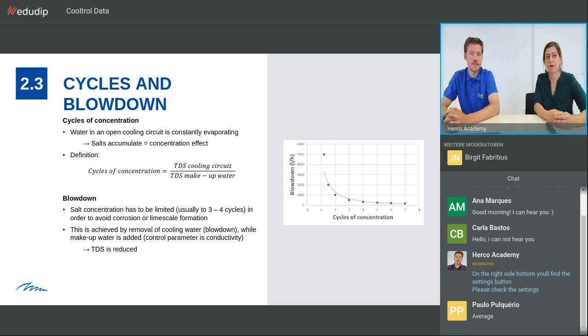Now, you can imagine if we allow the TDS to go up in the circuit, we have a lot of cycles of concentration. That would mean we have a lot less makeup water demand. Brilliant, right? Because less makeup water. Less waste. Exactly. So you don't have to spend money on the makeup water, but of course, there is a problem. As soon as the salt concentration gets too high, we can have either corrosion or limescale formation. So the salt concentration in the circuit has to be limited, and this is done with blowdown, also called bleed off. In that case, we remove cooling water via a valve, and makeup water is added to get the original water level again, thereby lowering the content of salt in the circuit.